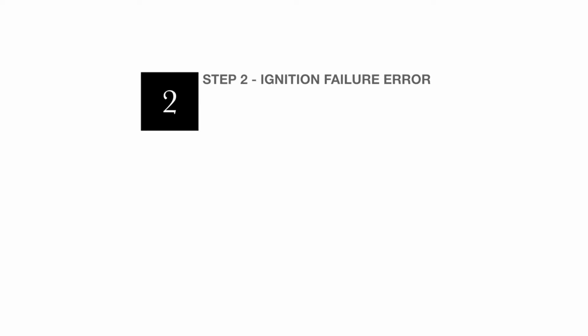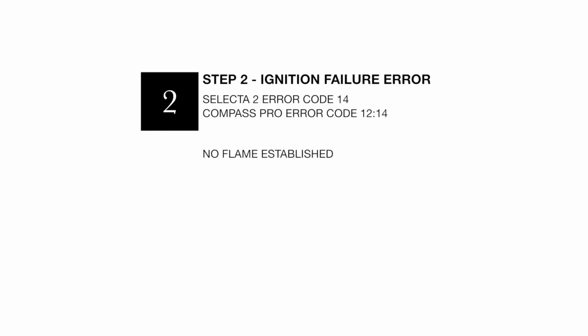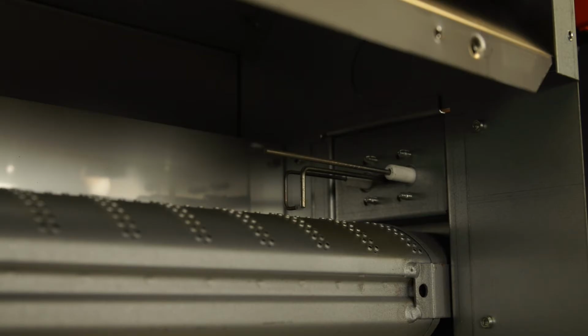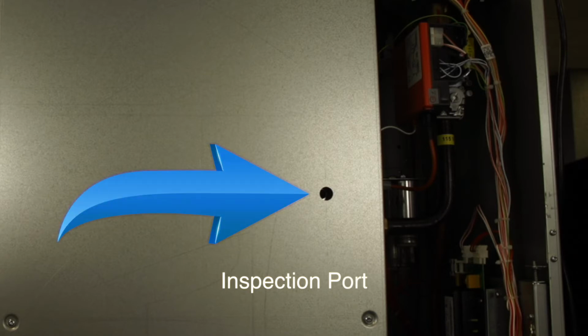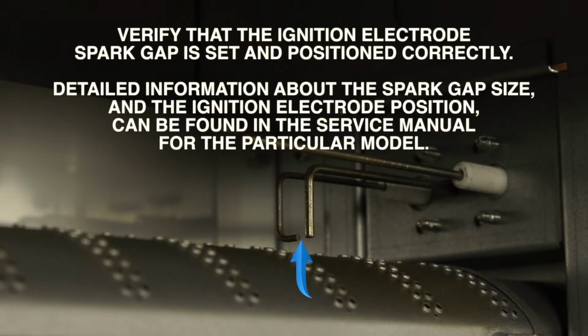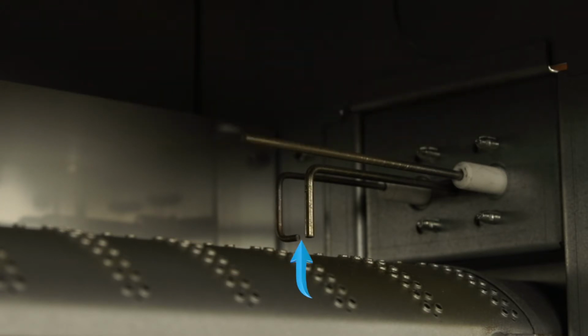Step 2. If no flame is established during an ignition attempt, check for the presence of a spark across the ignition spark gap. The spark can be heard as a clicking sound and can also be seen through an inspection port on most models. Verify that the ignition electrode spark gap is set and positioned correctly. Detailed information about the spark gap size and the ignition electrode position can be found in the service manual for the particular model.